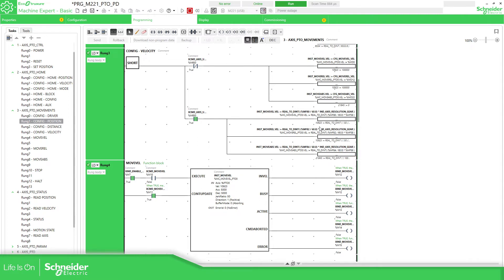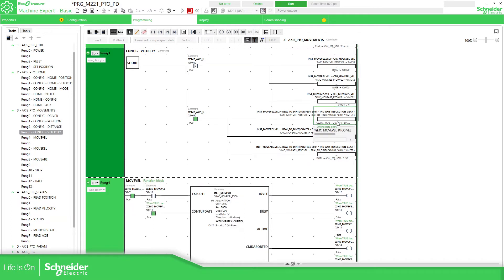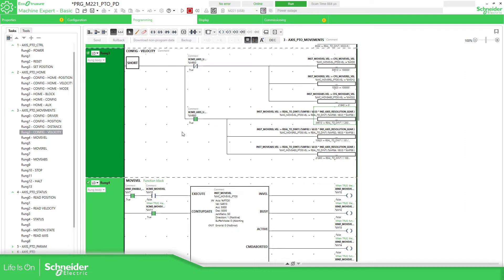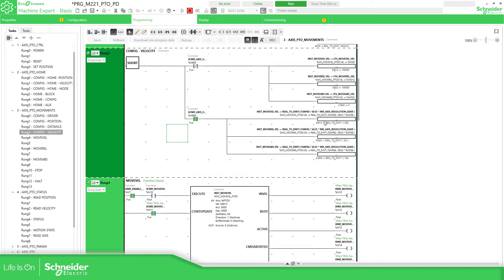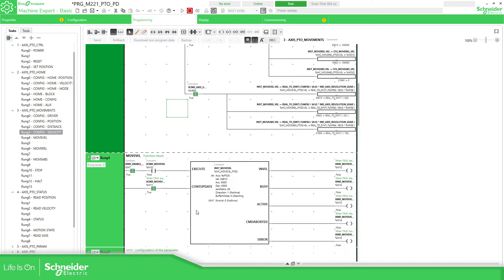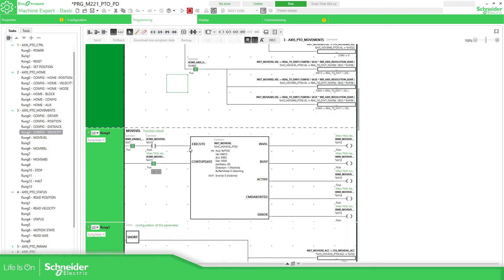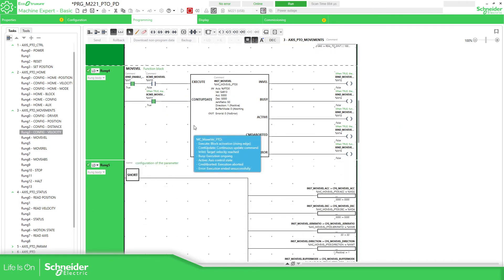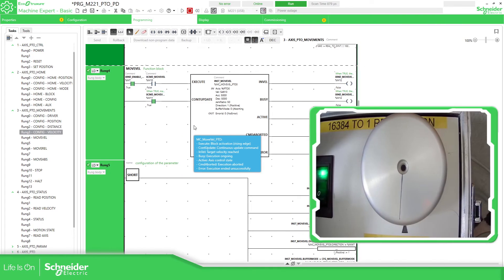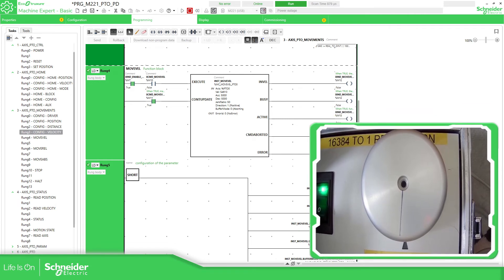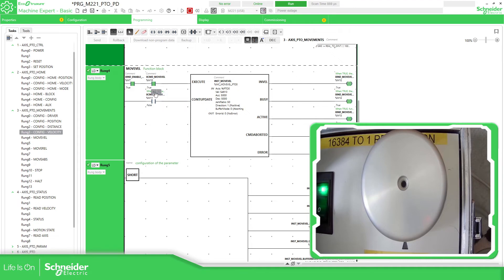So you can assign the value. In my case, I already created some formulas. So if you go over here, move velocity, I'm going to assign, for example, this variable, 100 RPM. You can see here, the frequency of the pulses calculation is 54 kilohertz approximately. So if we start the move velocity now, let me just change the view so you can see here this. So it will start moving faster and I'm going to uncheck this part so it will need to execute again to change the velocity. So there we go. It's moving. It's doing something.